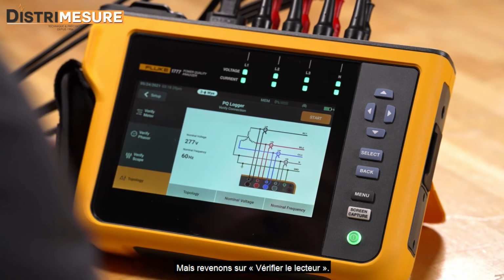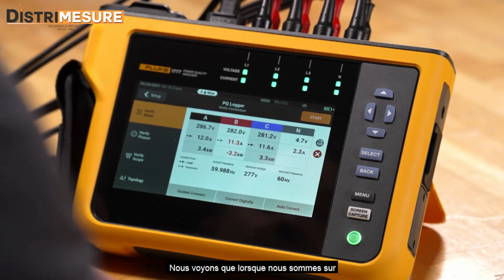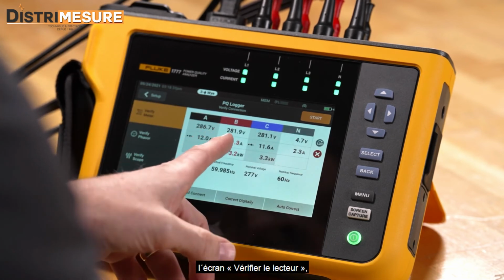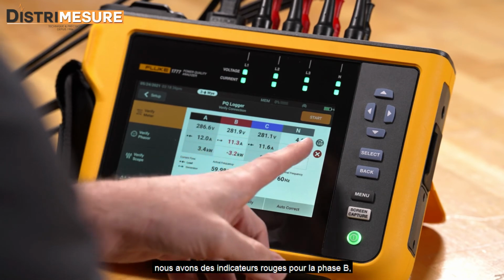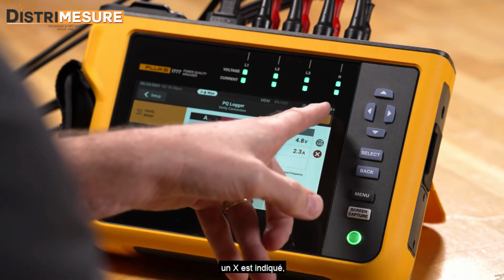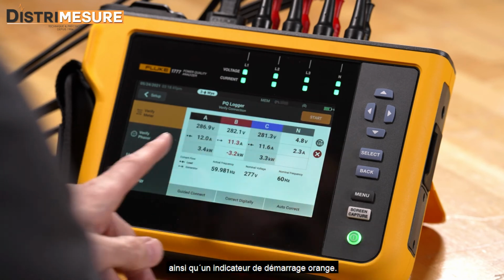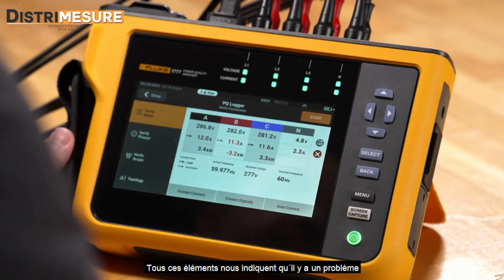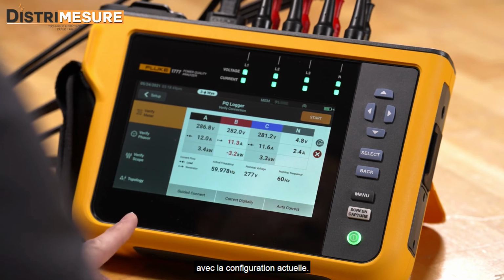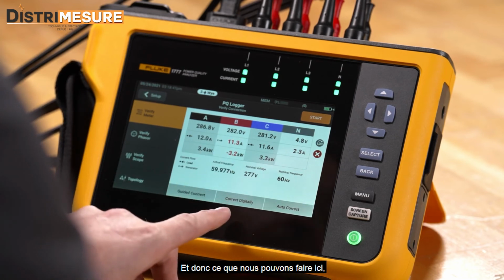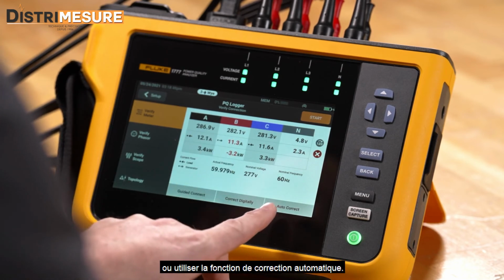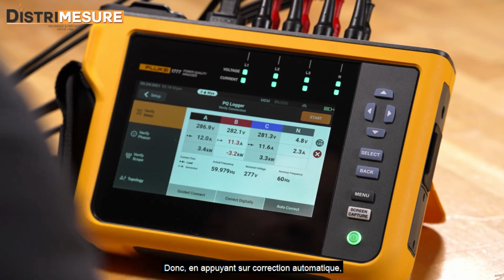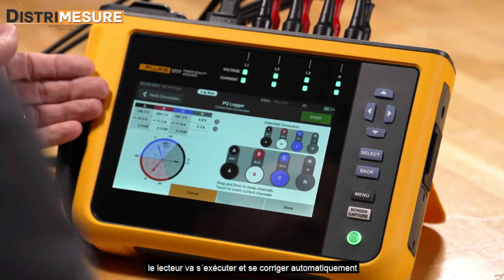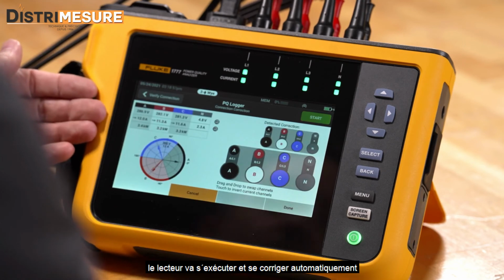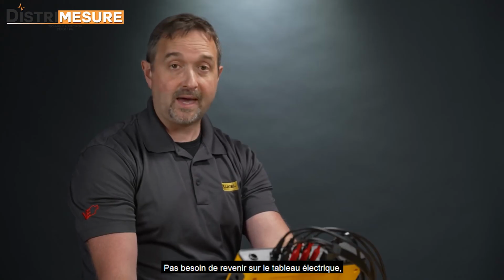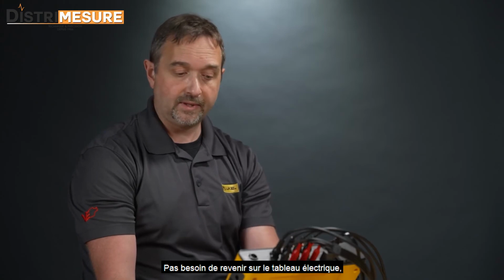But we'll go back to verify meter, and we'll see that in the verify meter screen we have red indicators for the B phase, there's an X indication, and an orange start indicator. All of these tell us that there's a problem with the current configuration. What we can do here is correct digitally, or we can do autocorrect. By tapping autocorrect, the meter will go through and fix itself and correct the problems. So there's no need to get back into the electrical panel; the fixes are all in place.